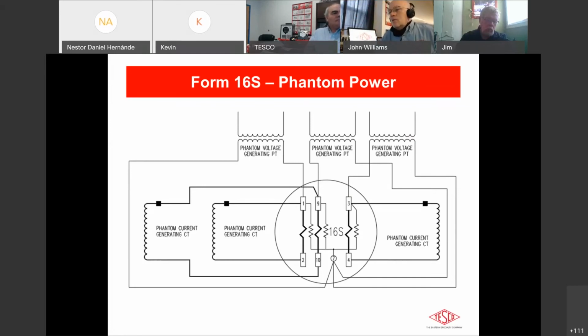On the TESCO boards, we do things a little bit differently there. When we do a disconnect test, we actually go off a standard line transformer that has up to a 1,000 VA capability to drive those disconnects. The digital sources used to drive the potential transformers there are usually rated around 90, 100 VA, something like that. So a lot of them are not capable of pushing through those disconnect relays.